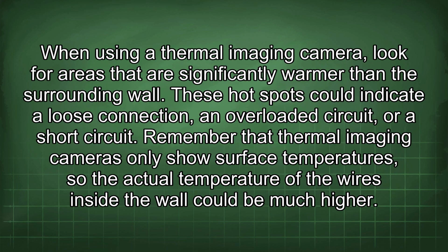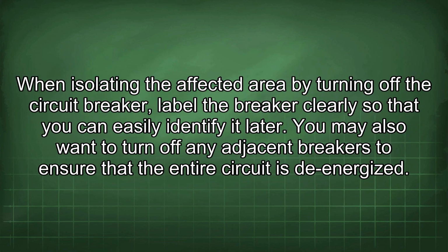When using a thermal imaging camera, look for areas that are significantly warmer than the surrounding wall. These hot spots could indicate a loose connection, an overloaded circuit, or a short circuit. Remember that thermal imaging cameras only show surface temperatures, so the actual temperature of the wires inside the wall could be much higher. When isolating the affected area by turning off the circuit breaker, label the breaker clearly so that you can easily identify it later. You may also want to turn off any adjacent breakers to ensure that the entire circuit is de-energized.